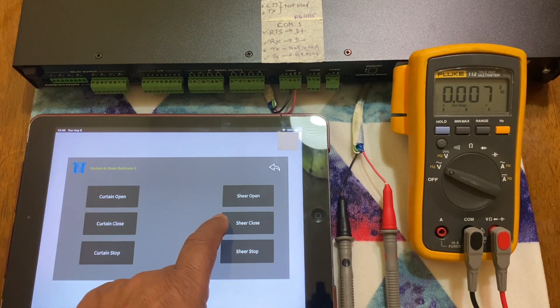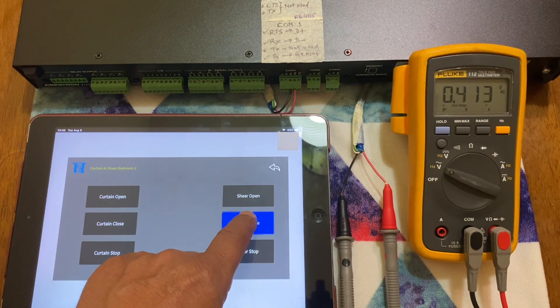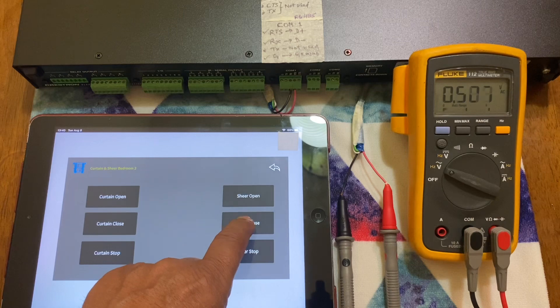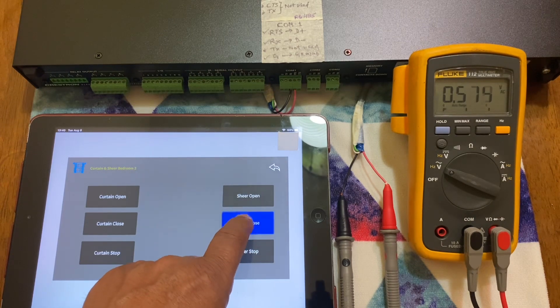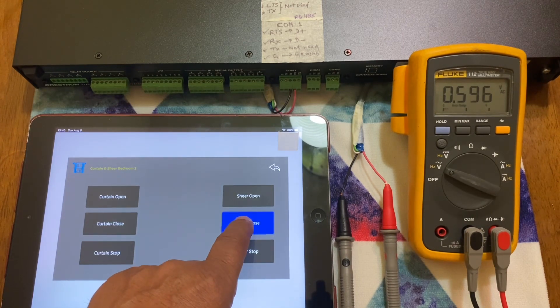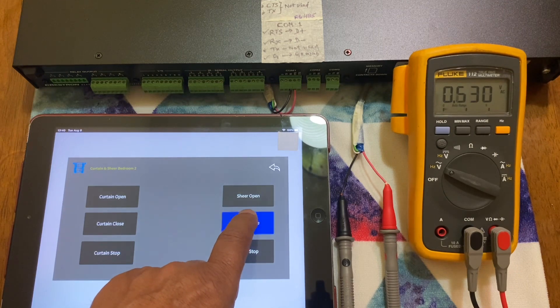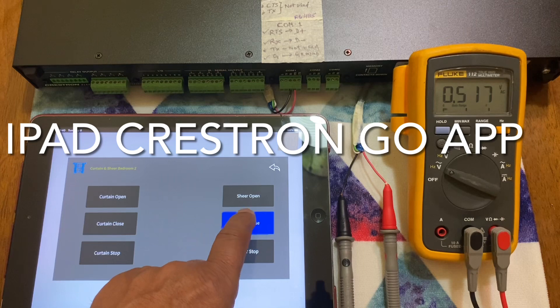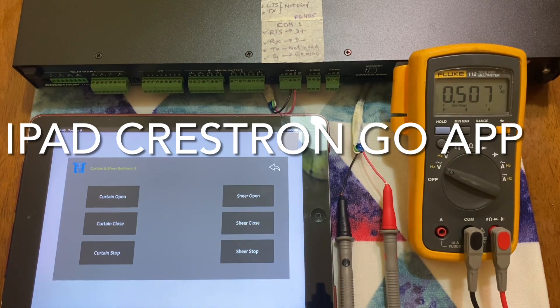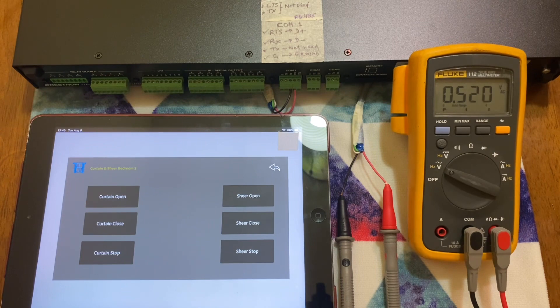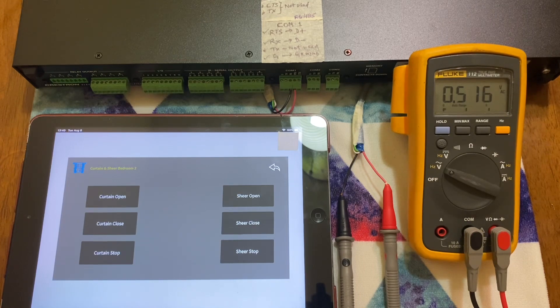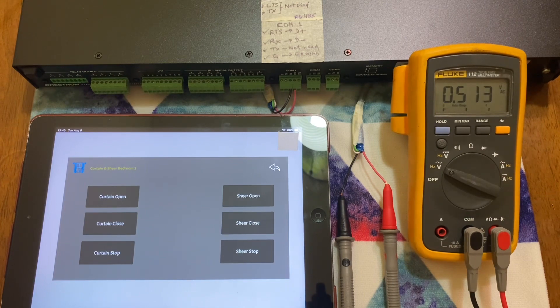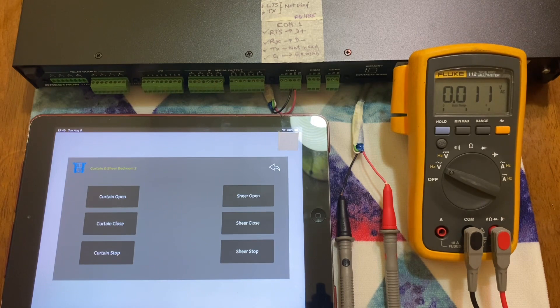Again I go here, I press sheer close. See, when I press it goes around 0.6 volts. You can see the pulse depending upon how I press it. It means from my iPad it's going to CP3, and from CP3 to COM1 RS485 output is coming fine. So my signal is okay. I just have to make sure I have proper protocol, the codes and the baud rate. That is most important. It will go after some time because it's trying to read. Maybe there are 50, 60 RS485 blinds or sheers in the whole project, so it tries to read all the status.